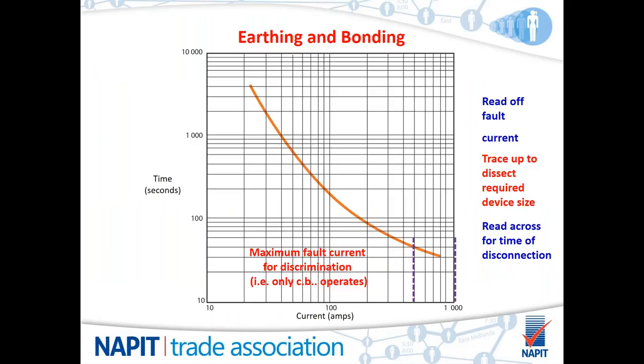Here we have the time current characteristic curves that are mentioned in Appendix 3. There is a graph for every type of protective device. The one we're looking at the minute with the curve is a fuse. There are graphs obviously for circuit breakers as well, but they have a backwards question mark type shape. The same process is used for finding disconnection times from these graphs. It's not shown on this slide, but in the top right-hand corner of the graphs in Appendix 3, you actually find a chart describing what the graph is about.